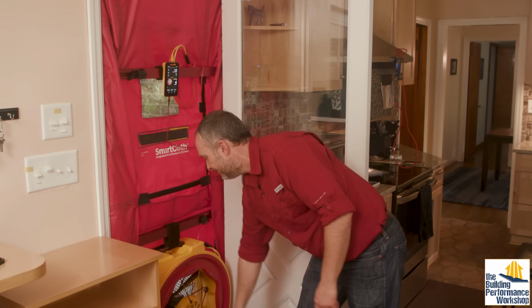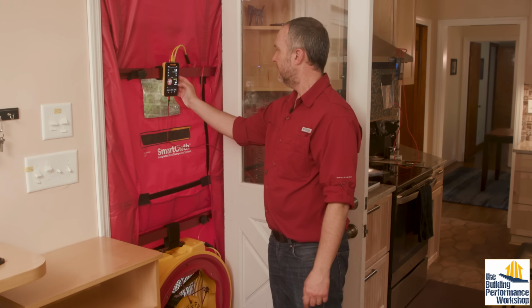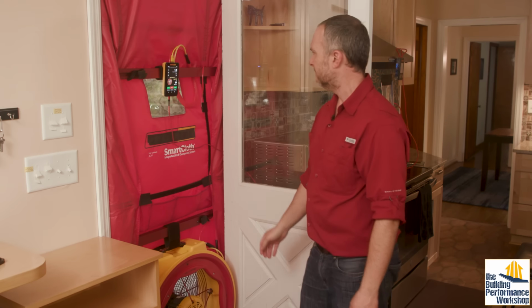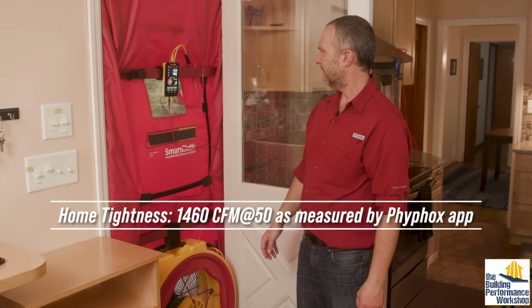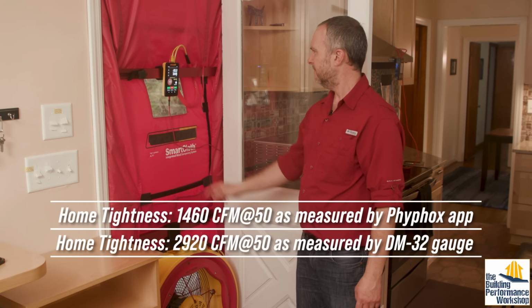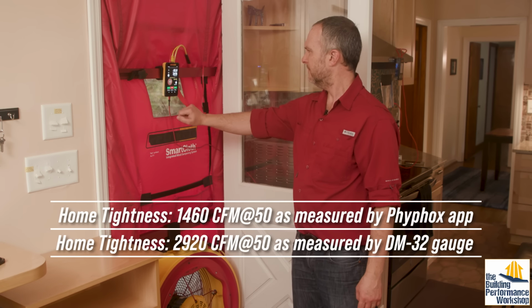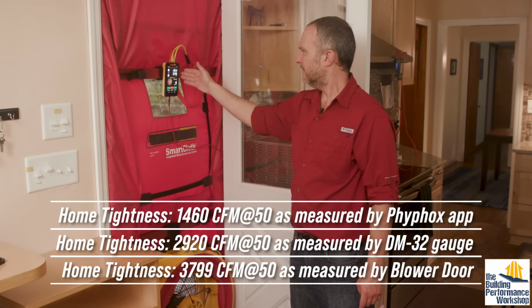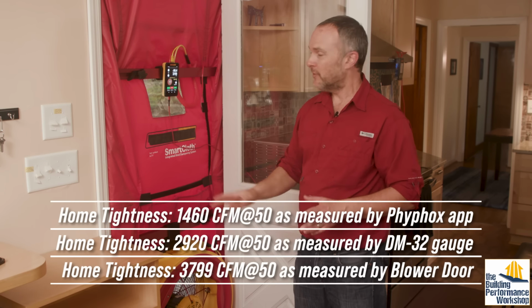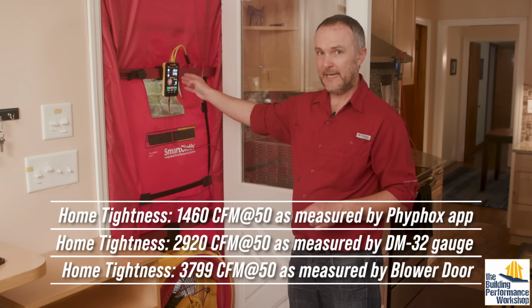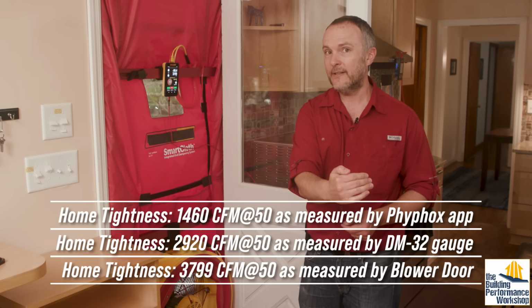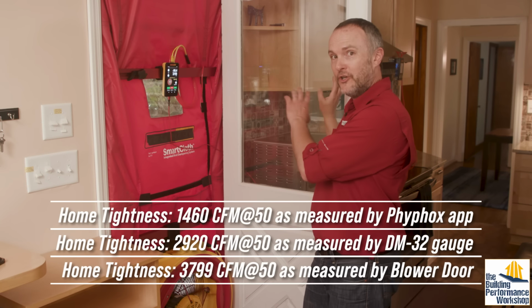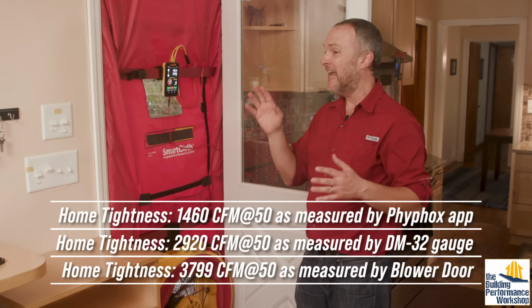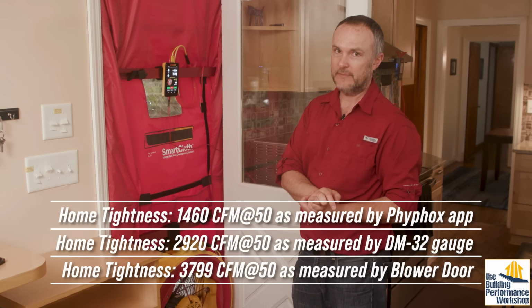Real test. All right, so actual number, 3,800 CFM, not 2,900 like the professional version of what we did over here said, definitely not what the phone said.